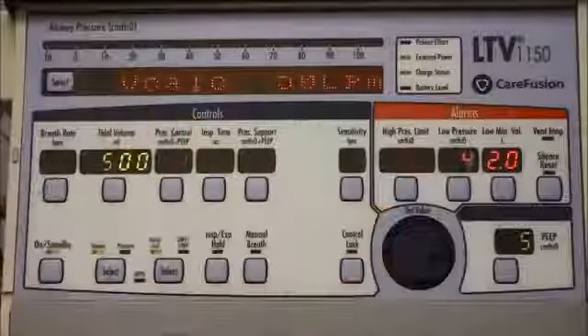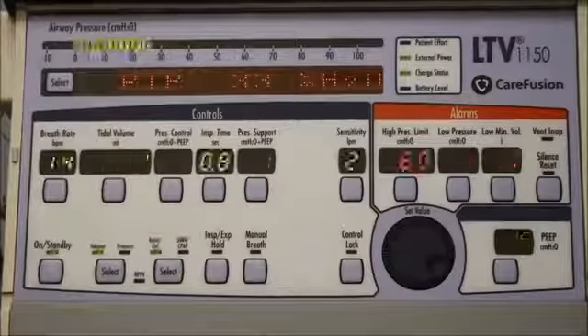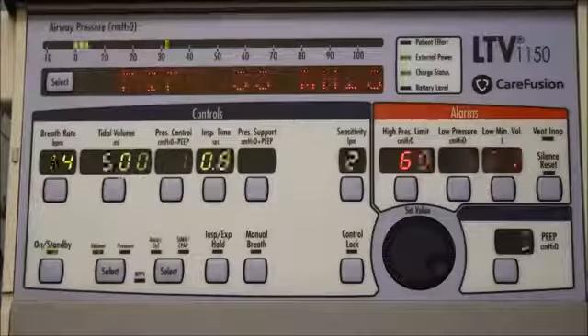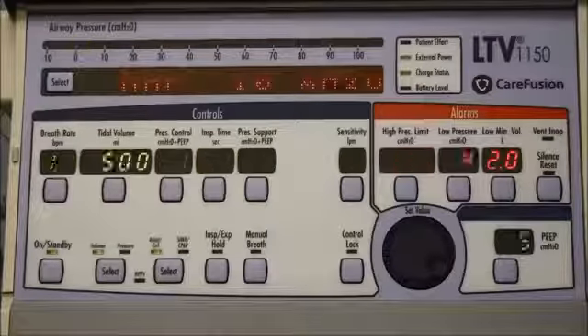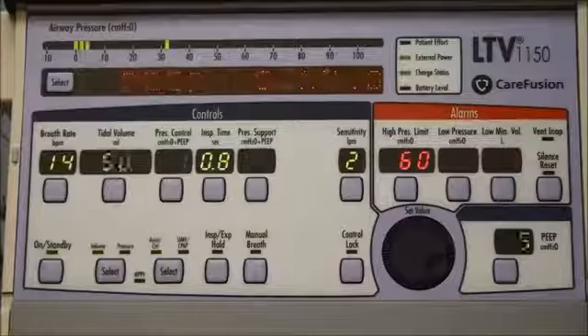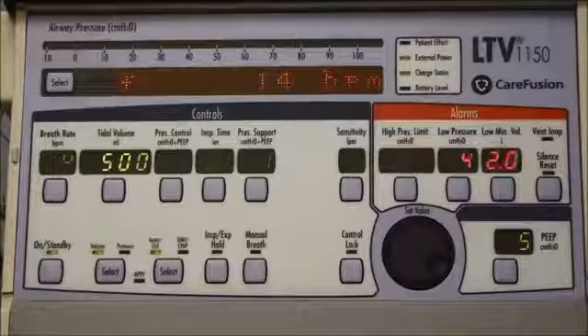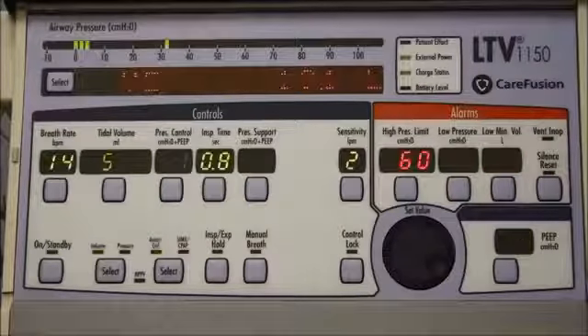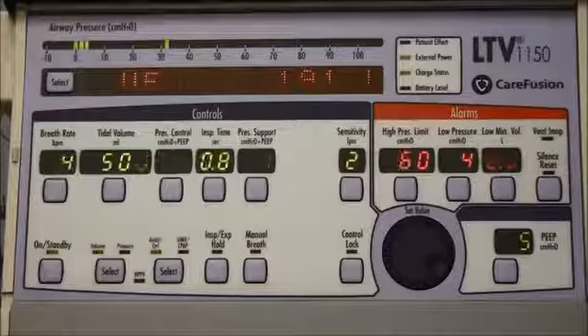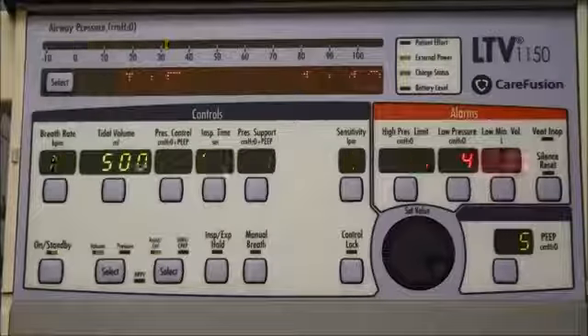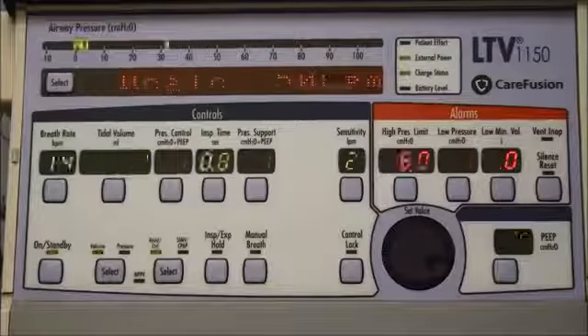The last alarm that's shown here is a low minute volume alarm, and that would also go off if there was some kind of leak or disconnect in your system. It can also be a problem at your patient. If the patient is having some sort of leak, or if the cuff on their trach tube has been deflated, you can also get a low minute volume alarm.